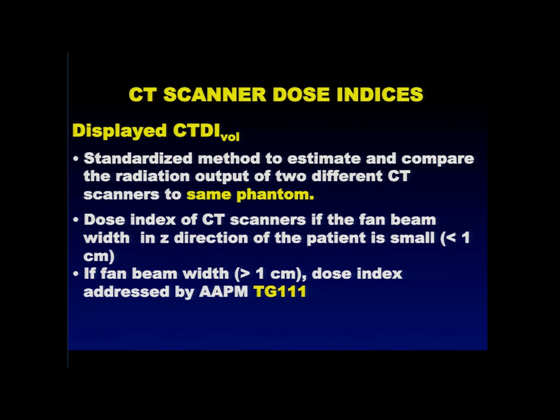Can I do that? Well, what do I use to make a CTDIvol measurement? I use a pencil chamber. How long is it? Somebody said, it's this long. Well, that's 100 millimeters or 10 centimeters. I'd need a pencil chamber 70 centimeters long to capture all the dose. So our CTDIvol measurements today are too low. They do not reflect reality.